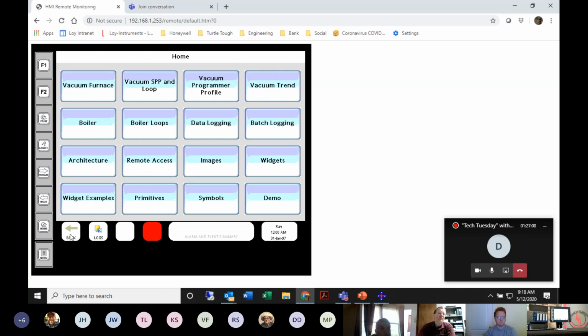You'll see at the very bottom where it has the back, it has logs, diagnostics, alarms, it has an event window, and then it has the date and time with run in the bottom right hand side. This is a standard display that we use quite a bit because it is kind of like the scoreboard. It doesn't matter what display you're navigating to, this will always be on the bottom of each one of the displays because we feel that the diagnostics and alarms are pretty critical in all applications.